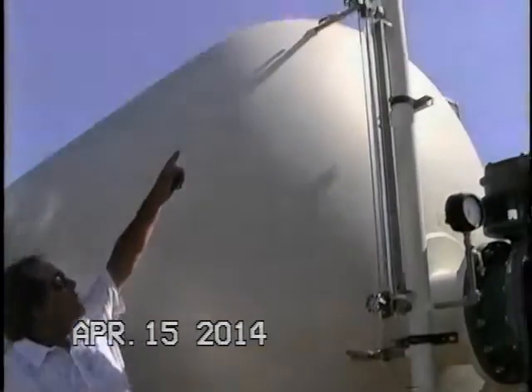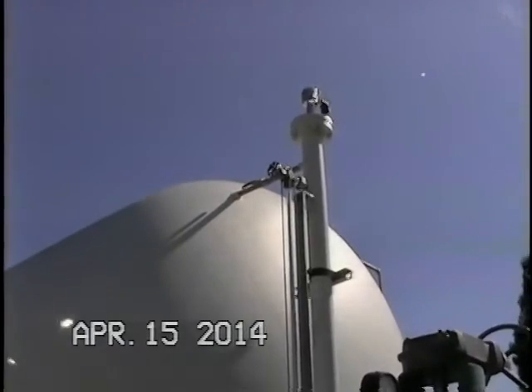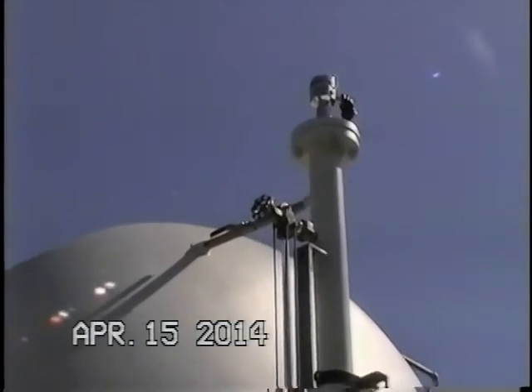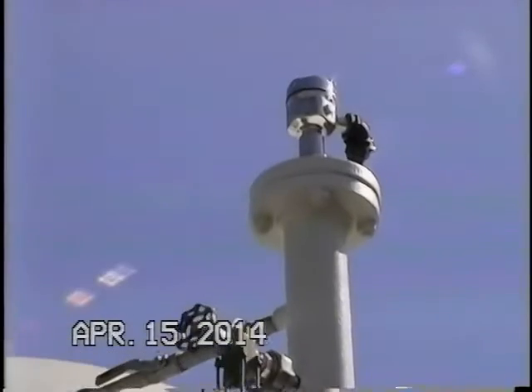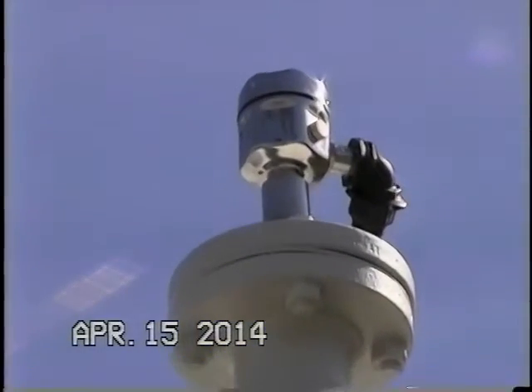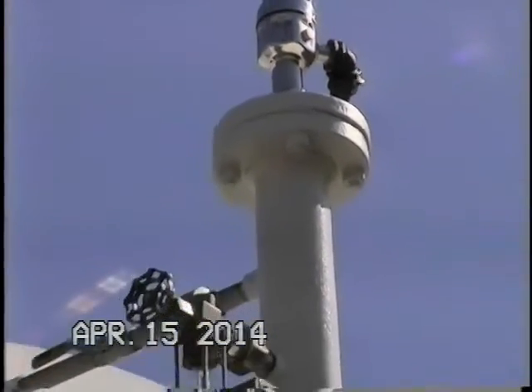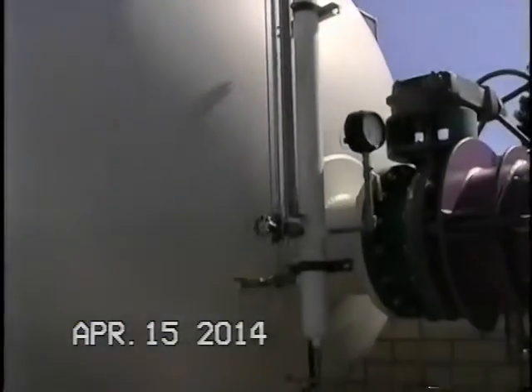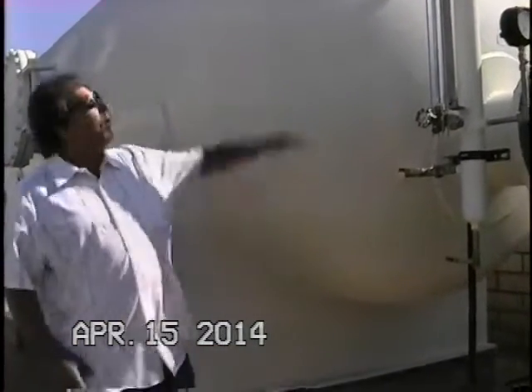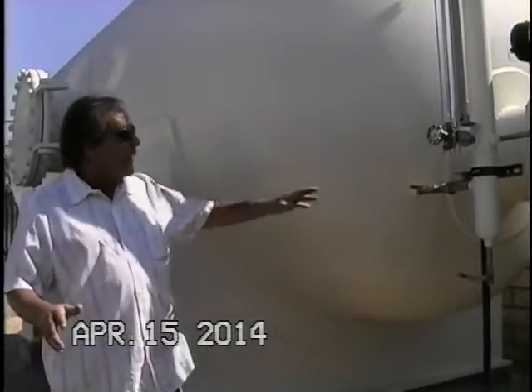At the top, there's a cap. It has a couple of buttons, and you press both. What you do first of all is empty out the probe well completely. Push both the buttons until the lights start flashing, and that will calibrate the empty. Then you fill it all the way up to the top. The only way you can accomplish that is to make sure that when it's empty, you got all the pressure out. It should have no air pressure, no water, nothing.